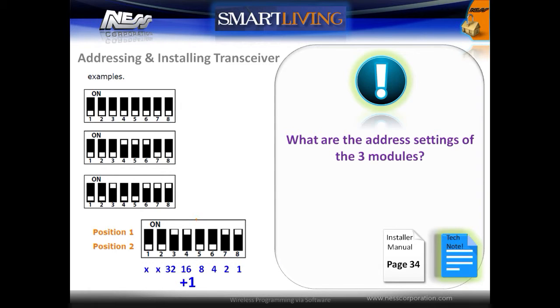Example 1 has all switches off and is classed as address 1. The next example has switches 4, 5 and 6 on, which equals 28 plus 1, equals address 29. The last example has switches 3, 6, 7 and 8 on, which equal 39. Adding 1 gives address 40.